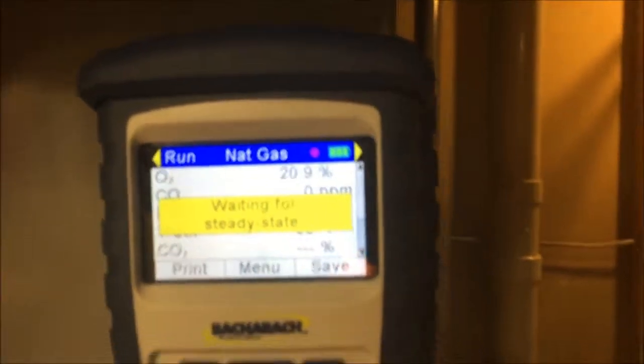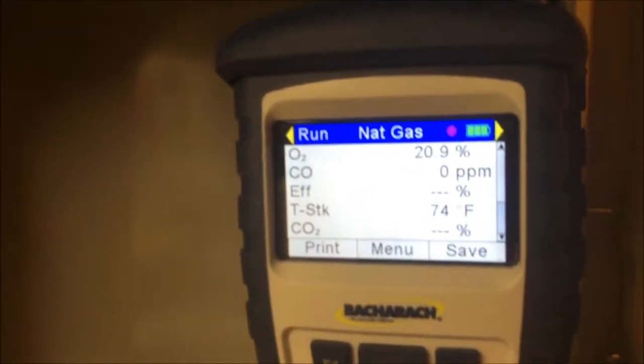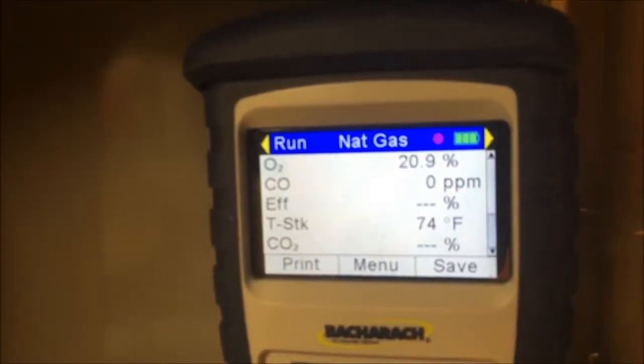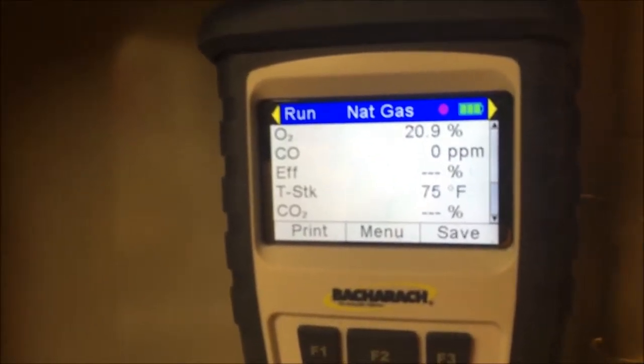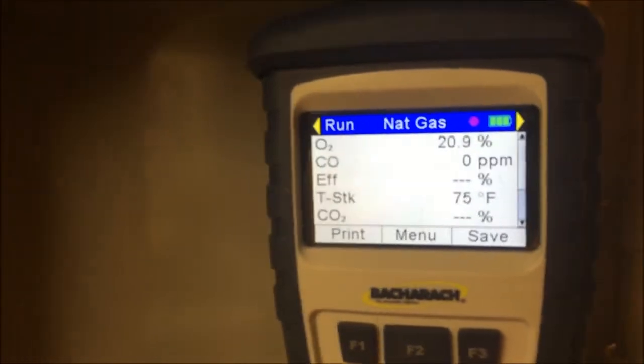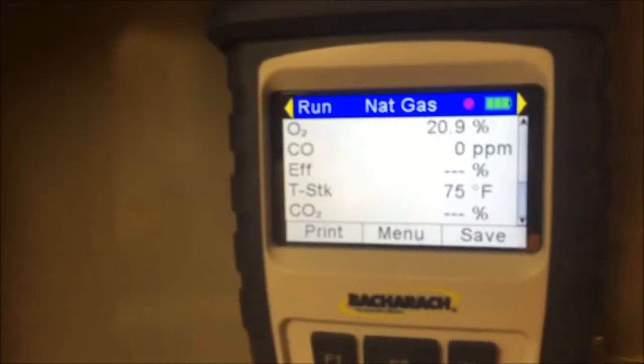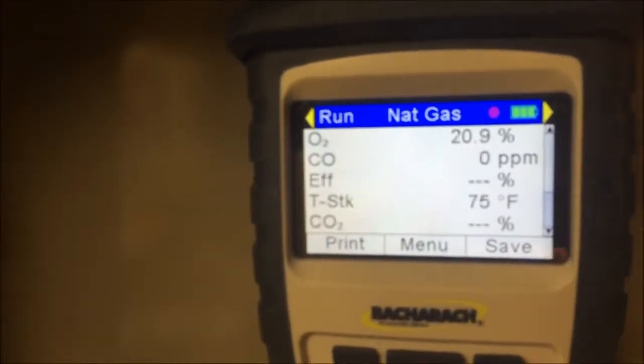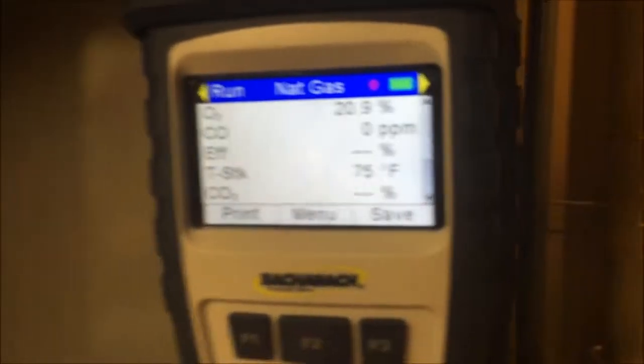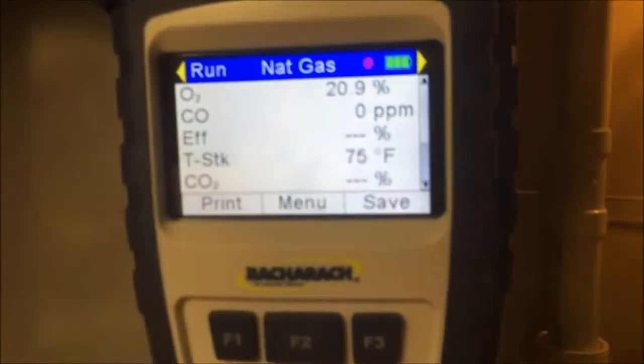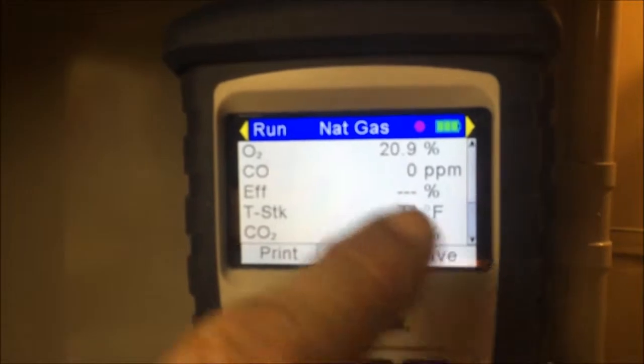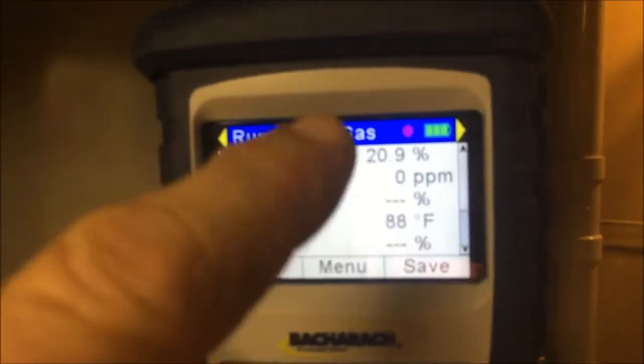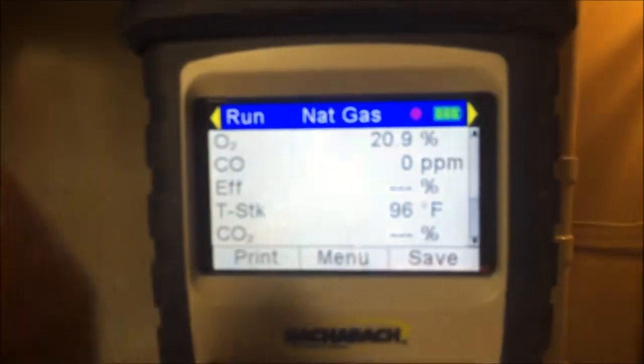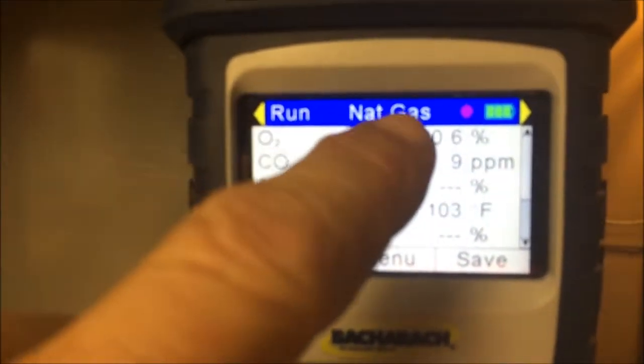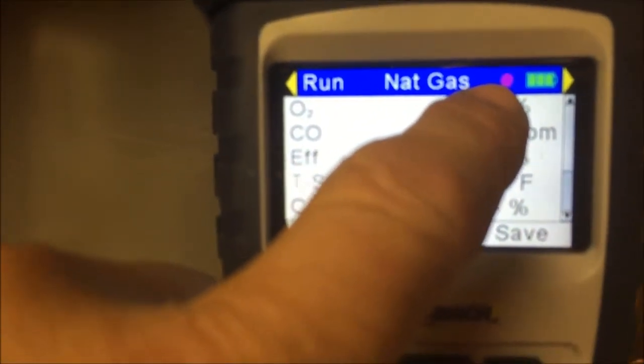What this thing does have, it's waiting for steady state. So if this doesn't heat the house up before I get to the steady state, what it will do on low fire, if it'll last long enough on low fire, once the temperatures and everything settle down, it'll say, okay, I'm good, and you will see this light right here change color after it. If you miss it, it'll say has come to steady state. It's like a yellow dialog box, and if you miss it, like you turn around to do something else real quick and you look back, this will actually change color. Instead of being, it looks purple to me right now, it'll turn to a blue.